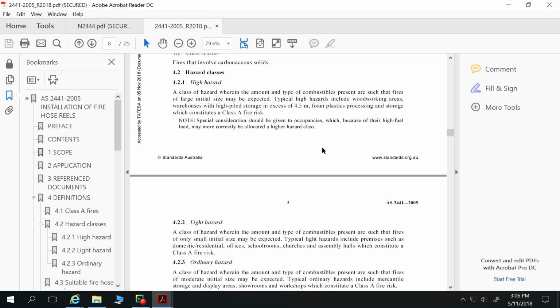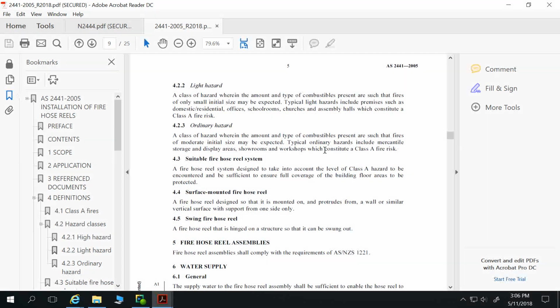So light hazard, I'll scroll that up. Light hazard is a class of hazard wherein the amount and type of combustibles present are such that fires of only small initial size may be expected. Typical light hazards include premises such as domestic/residential, offices, schoolrooms, churches and assembly halls which constitute Class A fire risk. So that's sounding a bit like our upper floors. And then ordinary hazard, a class of hazard wherein the amount and type of combustibles present are such that fires of moderate initial size may be expected. Typical ordinary hazards include mercantile storage and display areas, showrooms, and workshops which constitute a Class A fire risk. So that's possibly our ground floor. That's sounding a lot like our ground floor. So we've got two hazards we'd be interested in for that.